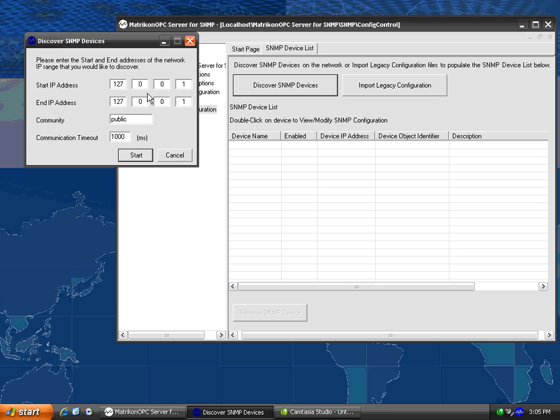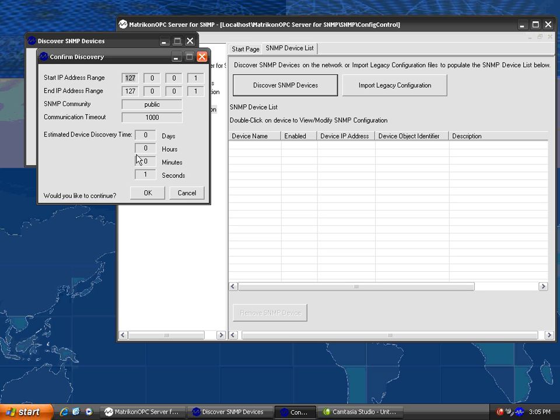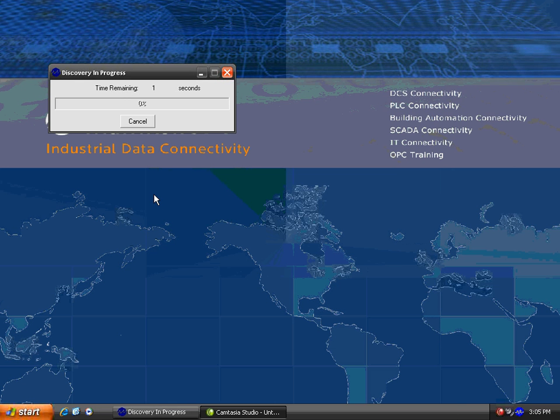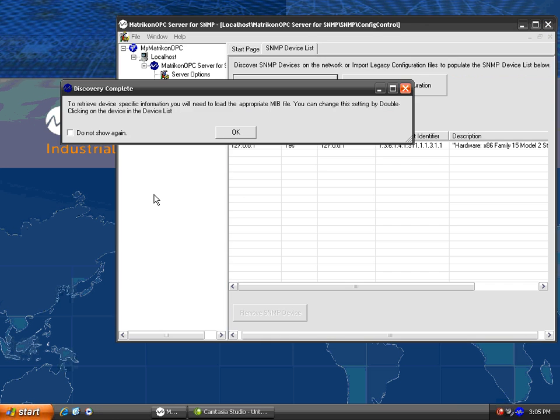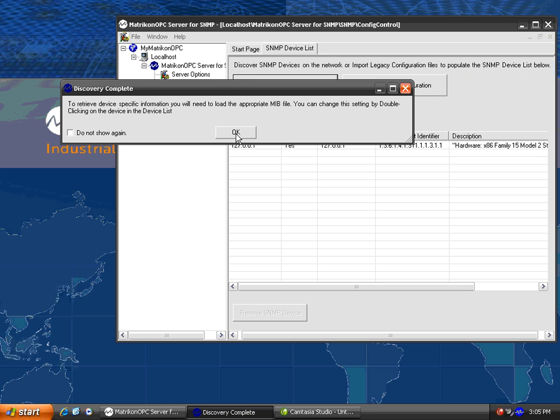The software gives me a summary on how long this thinks it will take. After searching, it comes up with some devices. Now by default, it will choose a generic MIB file. If you have a vendor supplied MIB file for your device, you could load it separately.